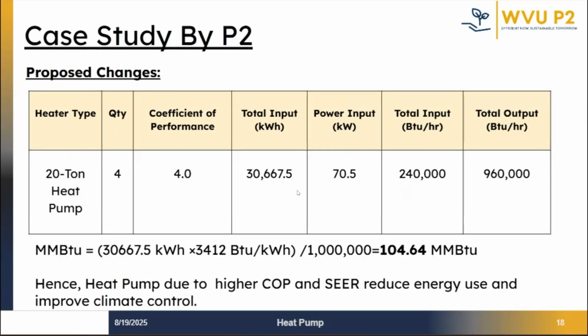Given the area of interest, we recommended replacing the natural gas heaters with a system using 4 20-ton heat pumps with associated equipment. The recommended system will provide 960,000 BTU per hour of heating output, which closely approximates the 855,000 output of the current systems. By switching to heat pumps for the warehouse, it is estimated that these changes will vastly improve the energy efficiency due to the higher coefficient of performance and seasonal energy efficiency ratio of these modern systems compared to current equipment. This will result in reduced energy consumption and better climate control across all areas.